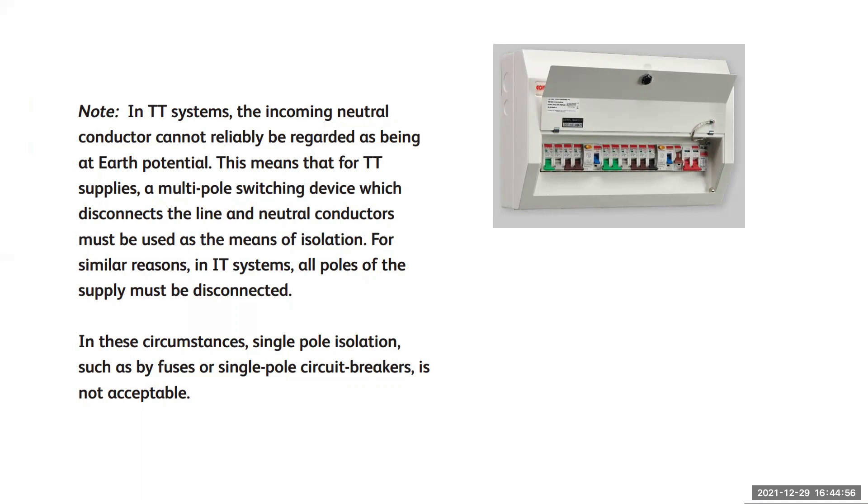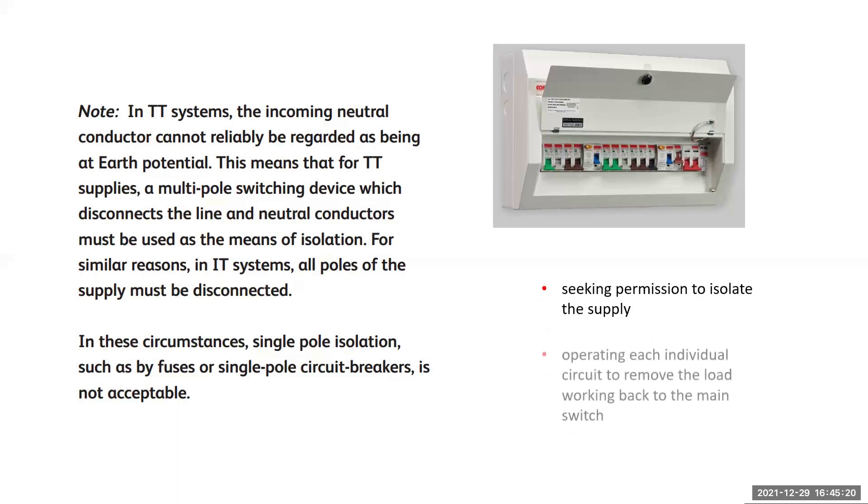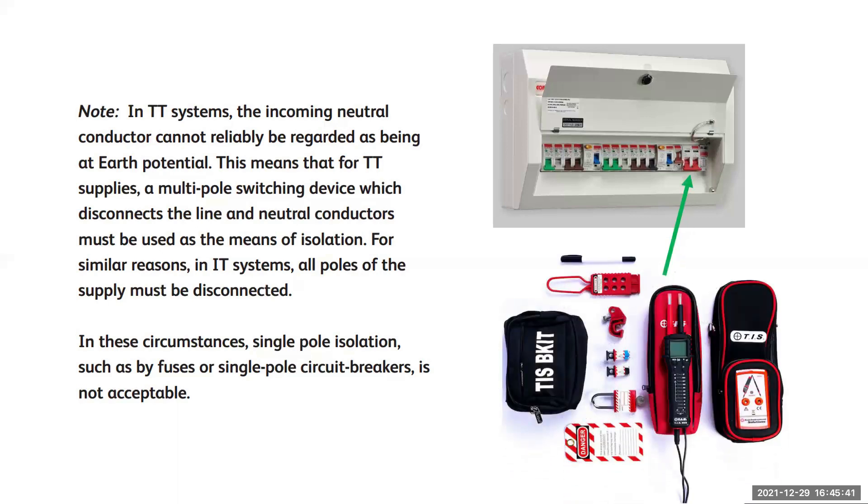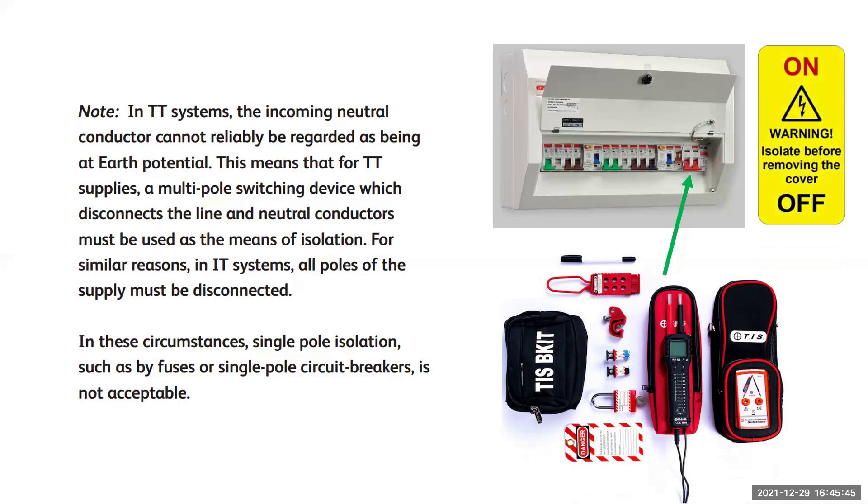It's also worth noting that the guidance from Electrical Safety First is that single pole devices are not suitable for TT systems or IT systems — multi-pole switching devices capable of isolating line and neutral conductors should be used instead. So next time you're standing in front of a consumer unit or accessory looking to gain entry to the live parts, don't forget to seek permission to isolate the supply. Remember that the main switch could be an isolator and not a switch, meaning that it may not be designed to be turned off under load. In this case, operate each individual circuit to remove the load and work your way to the main switch to avoid damaging it. Then secure the main switch in the off position with a suitable lockout kit. Most three phase boards have a red warning sticker beside the board that states 'isolate main switch before removing cover,' and yet they don't have them on a single phase board — I've always wondered why.